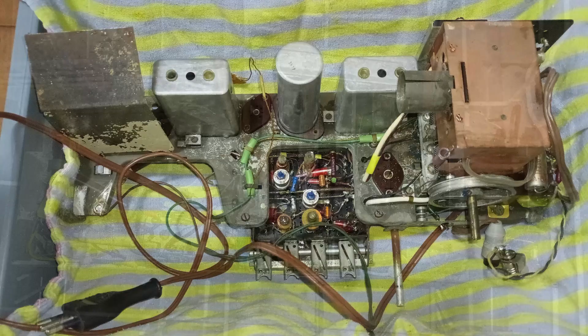This practice is definitely not recommended due to the presence of exposed coils with very fine wires that would break just with the dishwasher water jets. With a lot of luck, nothing was damaged any further. However, the dirt and dust were not the cause of the failure.